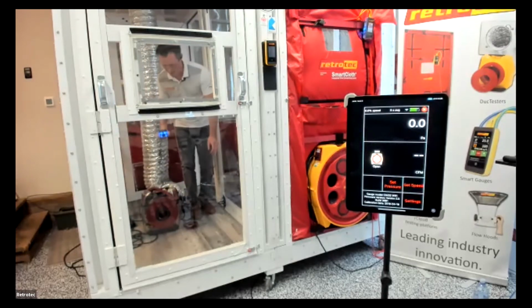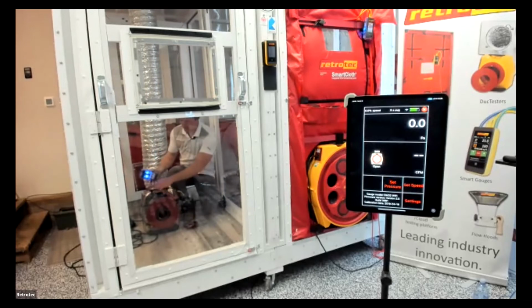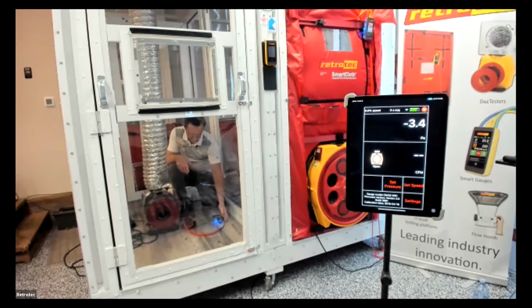And I'm going to hook this manometer up the exact same way that I did last time, using our color coding protocol. One thing that I'm going to do a little different this time is I'm not going to use the control from the gauge. I'm going to run this manually with the dial on the side of the fan. And I'm mainly doing that because I can get there faster. Sometimes when you let the gauge do it automatically, it can take a little while to get there.